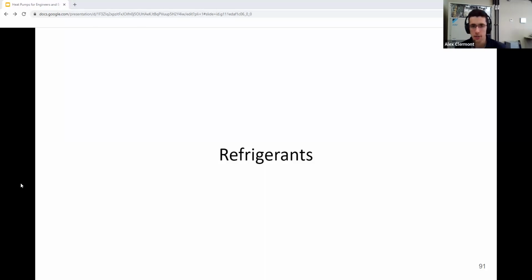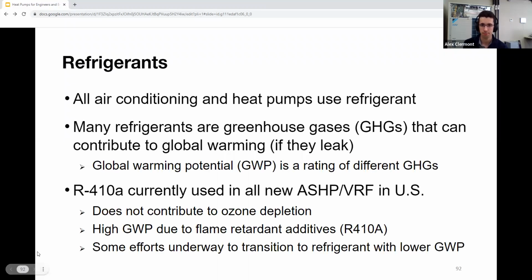We had a great question on refrigerants, so I figured that's something we would touch on now as well. We talked about that a little bit in the intro module, but we'll do a quick recap and talk about refrigerants. Something to keep in mind is that every single type of heat pump actually uses refrigerant. We'll be focusing on refrigerants for comfort cooling applications in this part, but every different heat pump can use a different refrigerant based on its application. Some are high pressure, some are medium pressure, some are low pressure refrigerants. In this section, we'll be focusing on high pressure refrigerants.